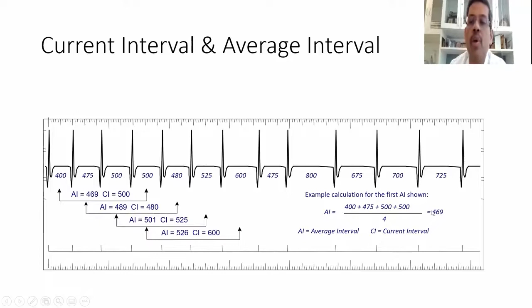And looking at this, it then bins each interval into either the sinus zone, VT zone, or VF zone. If both current and average interval are in the same zone, then it bins into that zone. For example, if both are sinus, it bins into the sinus zone. If both are VT, it bins into the VT zone. And if both are VF, it bins into the VF zone. If the current interval is faster, in a tachycardia or fibrillation zone, whereas the average interval is in the sinus zone, then the device does not bin that interval, and that is marked by a horizontal dash in the binning markers.